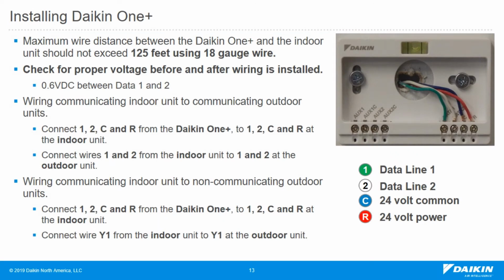Wiring the thermostat, we have 4 new connections: auxiliary 1 in and out, auxiliary 2 in and out. And we have the data 1 and 2 and the CR. Now the equipment is all labeled 1, 2, RC. And coming up to the thermostat, we'll have to reverse those wires for the CR. Most commonly, we're still using the 18-4 or larger wire that was existing in the home, and the red wire goes to R. So it's really more difficult to confuse, but the polarity is important. So make sure the R does go to the R.